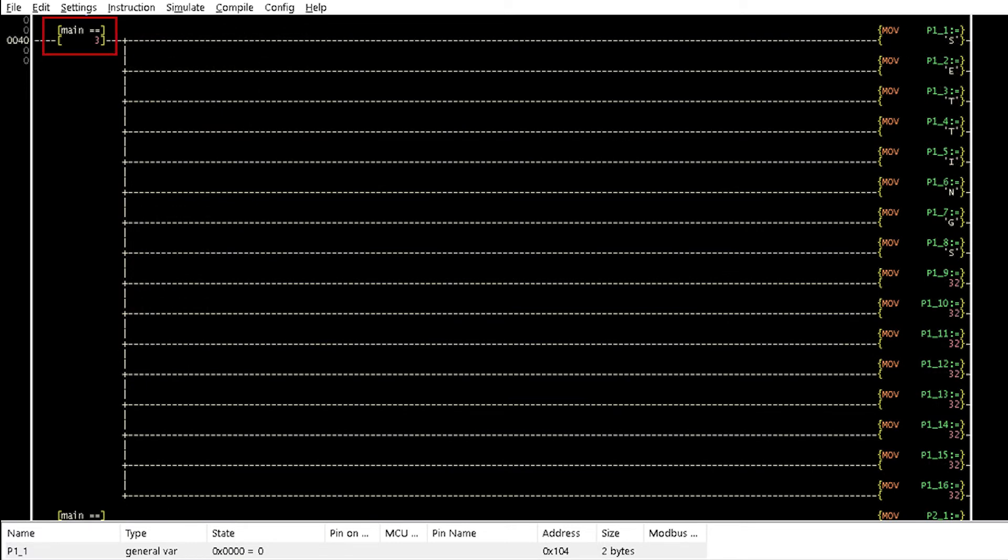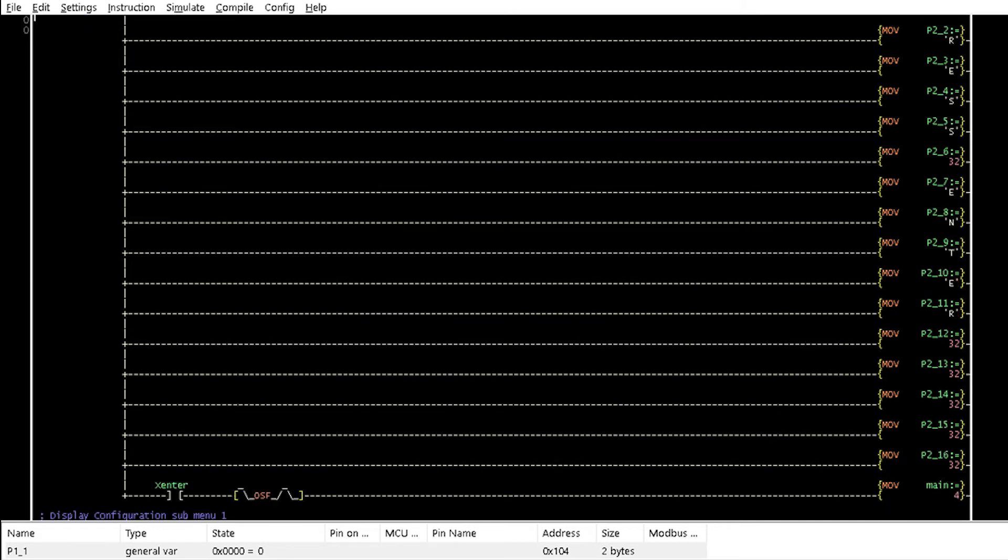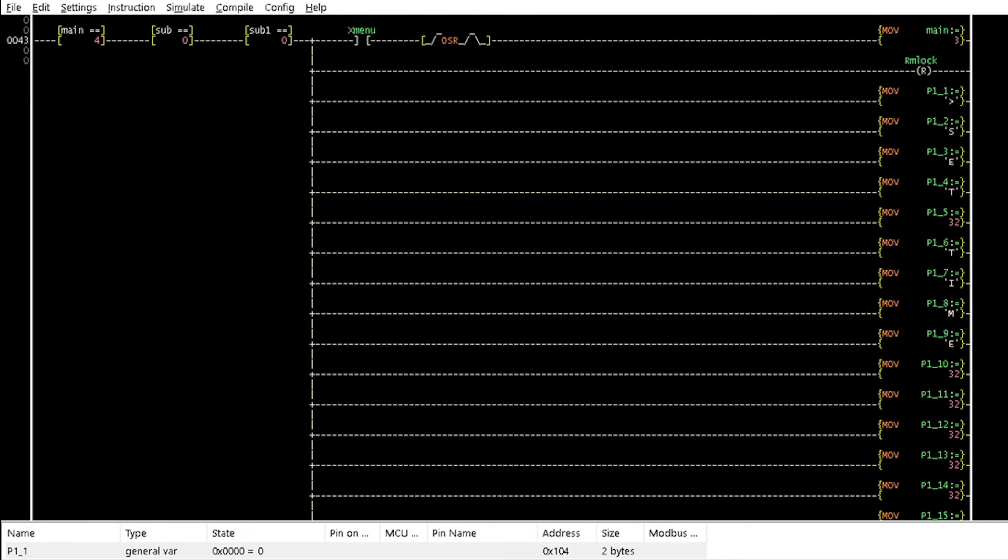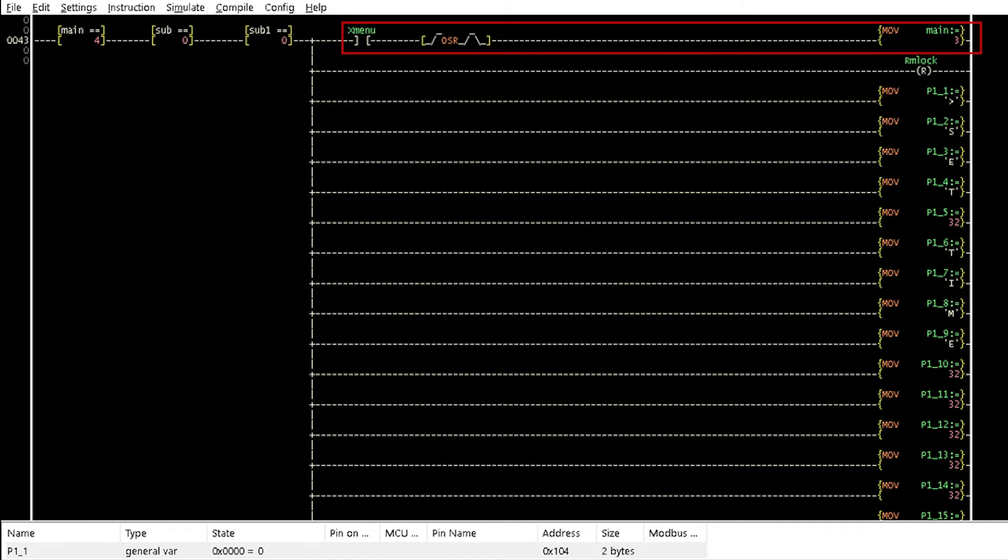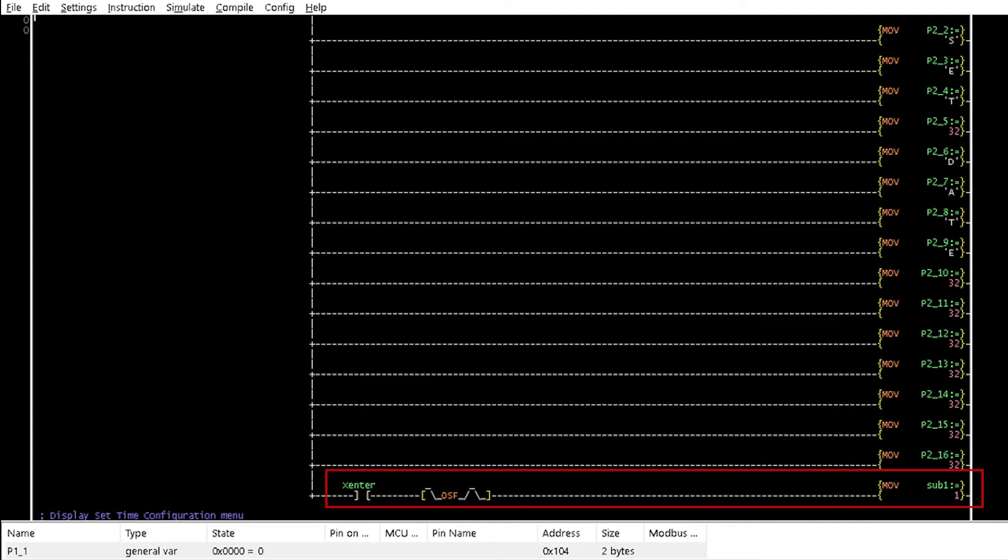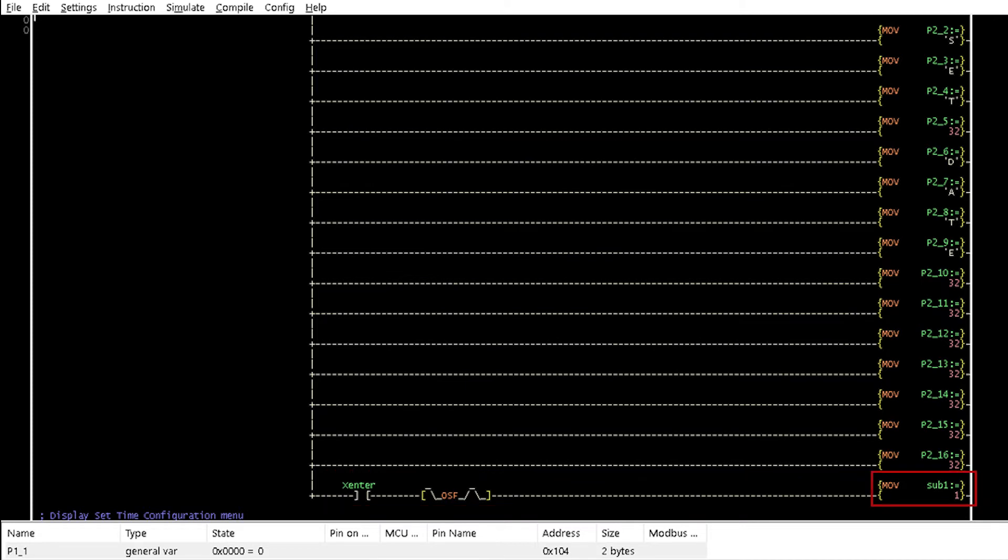When the variable main is equal to 3, Rungs 40 and 41 display the settings menu on the LCD. Pressing the enter button at this point makes the variable main equal to 4. It allows the submenu to be called up and subsequently the execution menu. Rungs 43 and 44 display set time and set date with the focus on set time. This section returns the display to the main menu when the menu button is pressed. And this section allows the execution menu to be accessed when the enter button is pressed by making sub1 equal to 1.